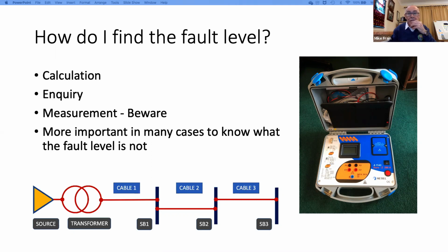And also by inquiry, if somebody is providing the power to the site, the person to tell you what the fault level is to that site is going to be the host distribution network operator, refer to them here. And then measurement, I mentioned measurement. You can measure arcing, you can measure prospective short circuit current, but not with a basic earth loop impedance tester, particularly if you're very close to a transformer. You need a piece of kit that is capable of an accuracy.